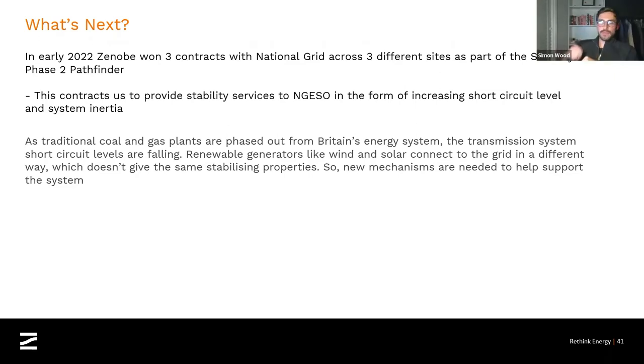So going back to what we were talking about right at the start, where a decentralized generation system has resulted in a loss of inertia, we've gone from lots of big spinning mass, if you think of all your large turbine type generators, so coal, nuclear, gas, they're all built around synchronous machines, big spinning mass with lots of inertia. A lot of that's gone, and the system therefore is far less stable. So National Grid, in order to increase the stability, are looking for ways in which to award services and contracts to customers to be able to provide that stability.